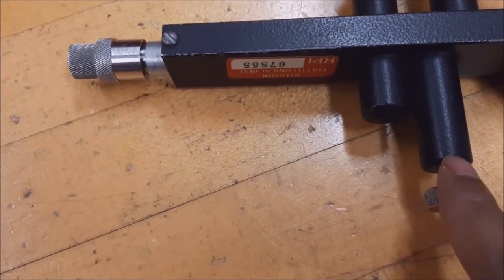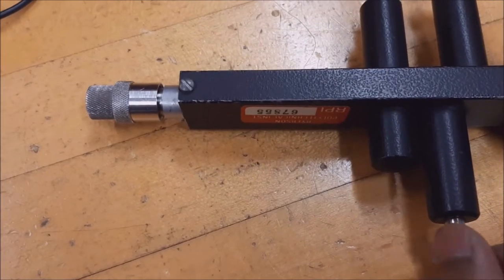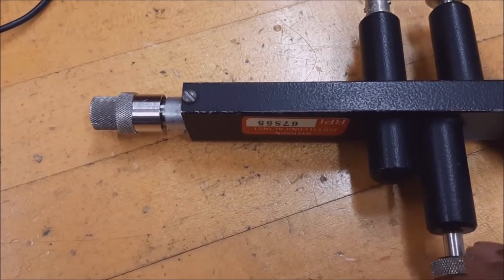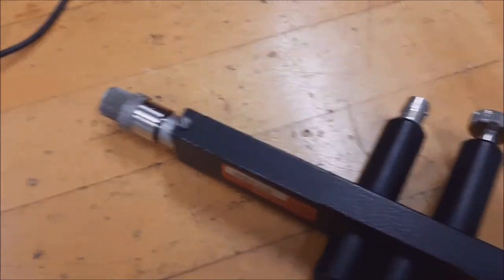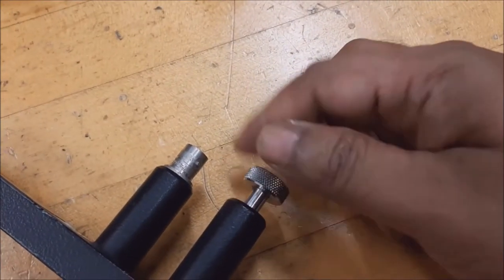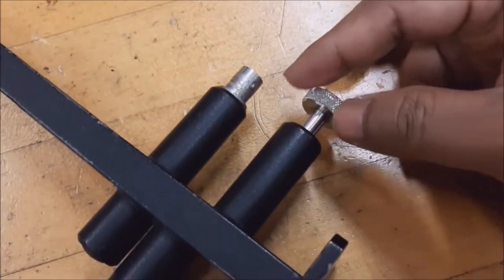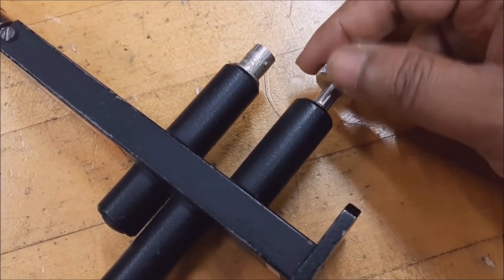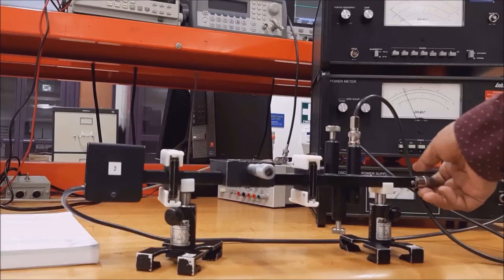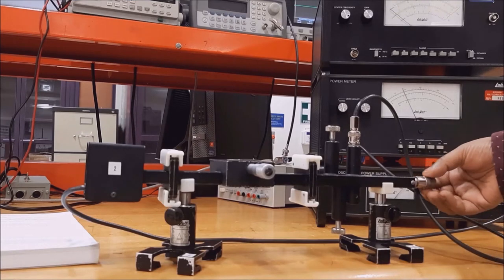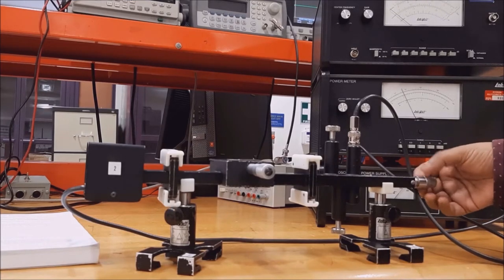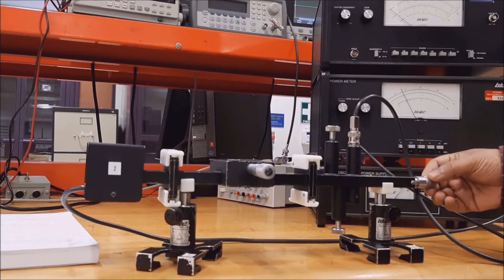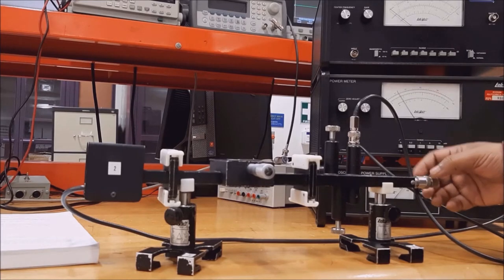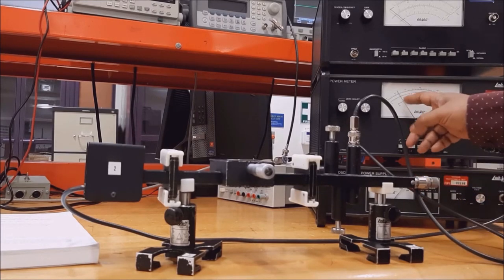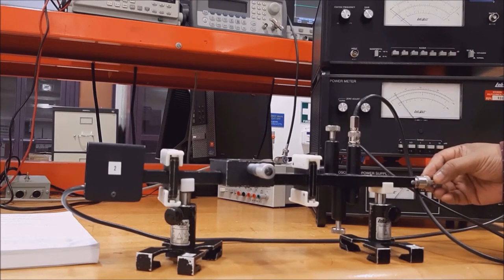There is another screw here that is called matching screw. So we have two matching screws. We can play with these matching screws to maximize the power level. So now we are going to show you how to get the maximum power level by using movable short circuit. You see, if you play with the short circuit, the power level will go up and down.